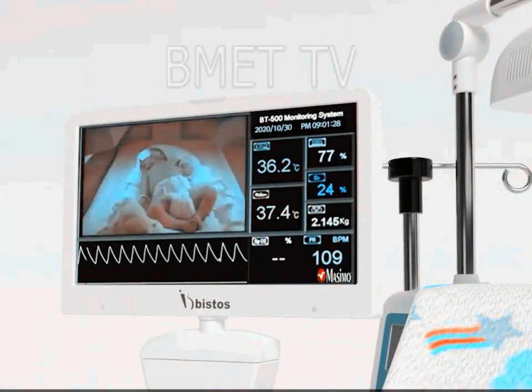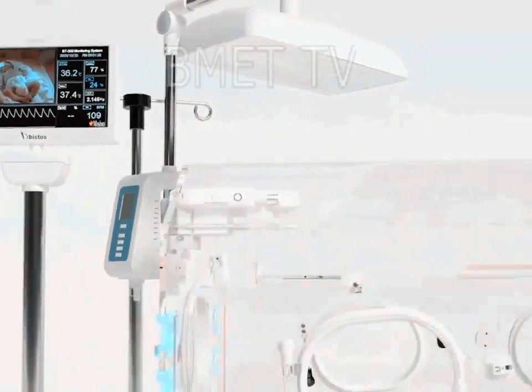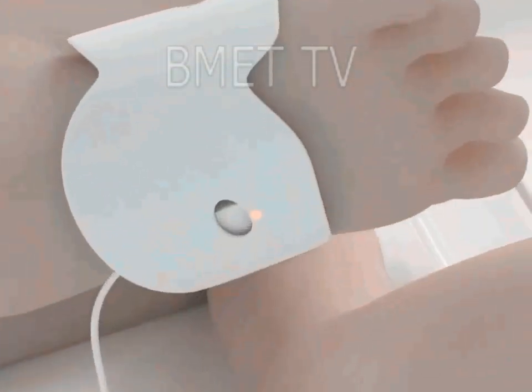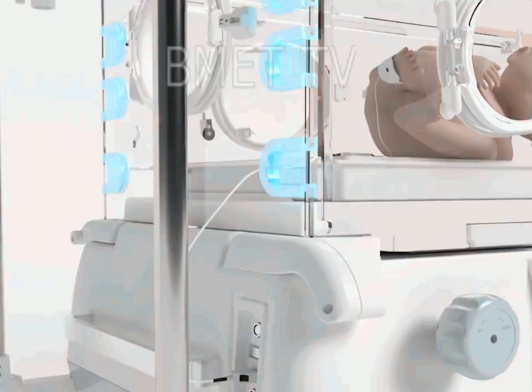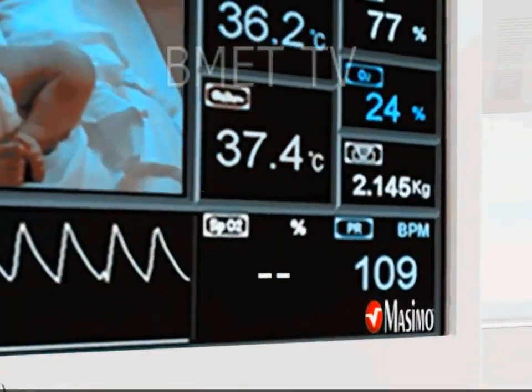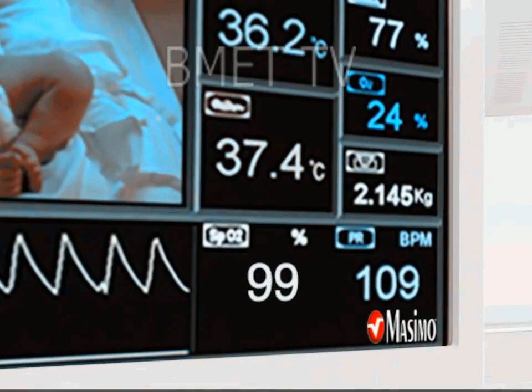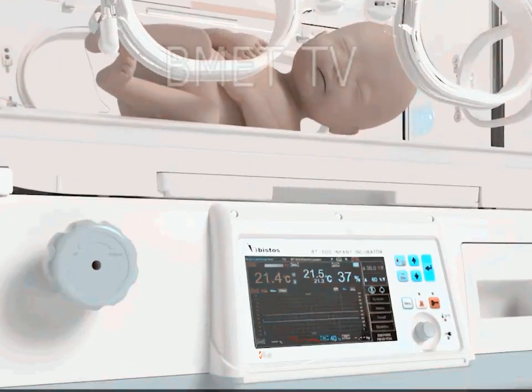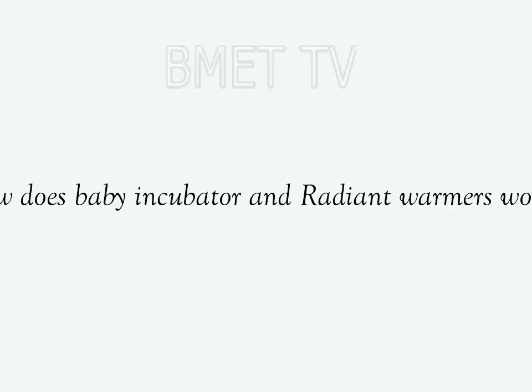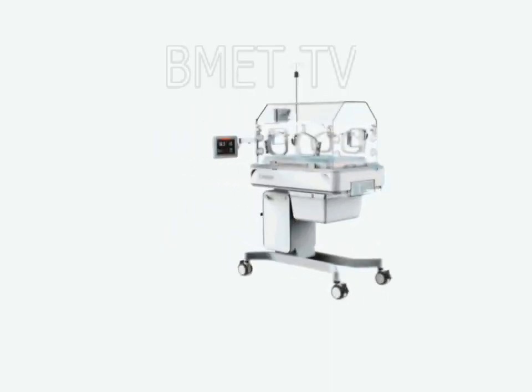Compared with incubators, the partition of body heat loss is quite different under radiant warmers. The major advantage of the radiant warmer is the easy access it provides to critically ill infants without disturbing the thermal environment. Its major disadvantage is the increase in insensible water loss produced by the radiant warmer. Most infants can be safely and adequately cared for in either an incubator or a radiant warmer bed. So, how do baby incubators and radiant warmers work? Let's start with baby incubators.